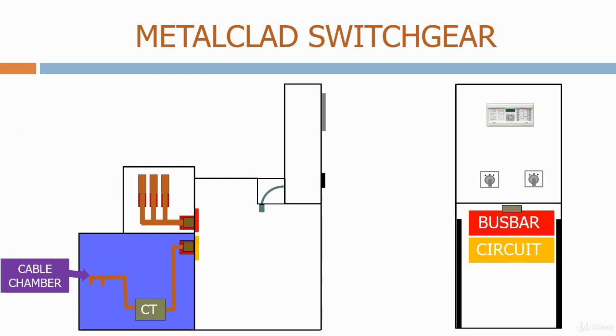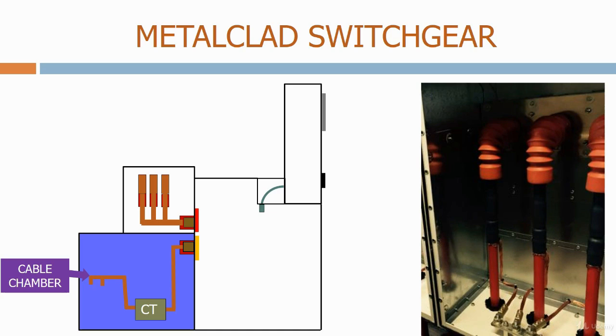Next, we have the cable chamber. This is where we bring in the feeder and incomer cables and connect the switchgear to the outside world. Here's a typical example. Cable chambers can have one cable per phase or multiple cables per phase. The cables pass through the grounded gland plate at the bottom of the chamber.